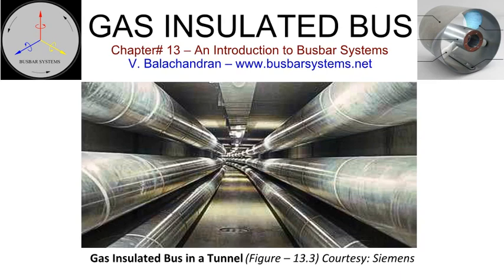The gas-insulated bus can be run horizontally, 3 phases side by side, in trenches, and vertically, 3 phases one above the other, in tunnels. Gas-insulated bus are also run on the sidewalls of tunnels meant for transportation by rail or road. Buried underground. Gas-insulated bus is buried horizontally at a depth determined by the terrain and soil conditions. This is the most economical way of running a gas-insulated bus. The enclosure needs to be protected against corrosion. Once the GIB is installed, the landscape can be brought to the original conditions.